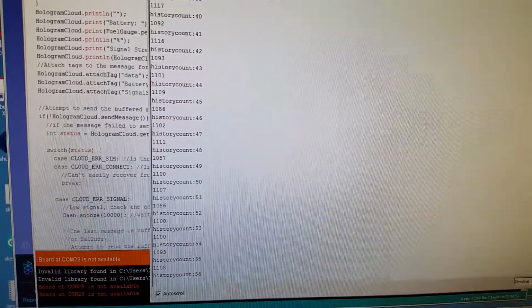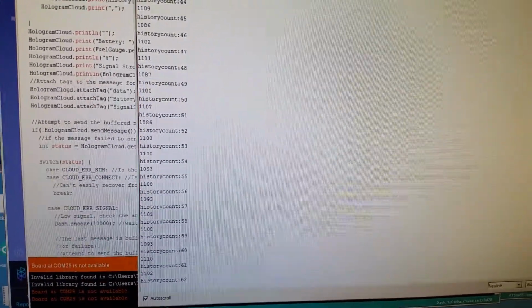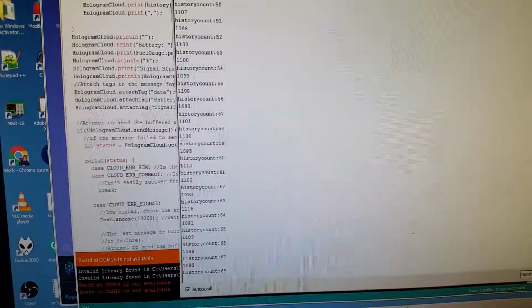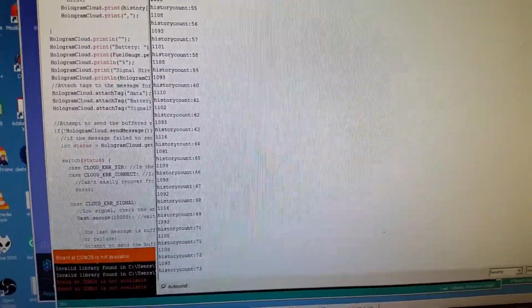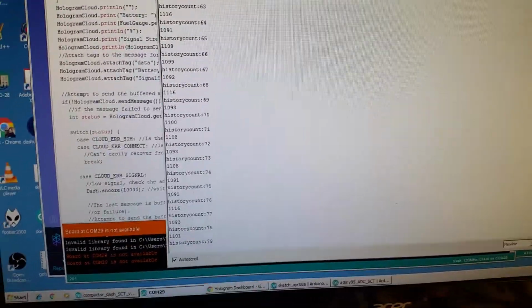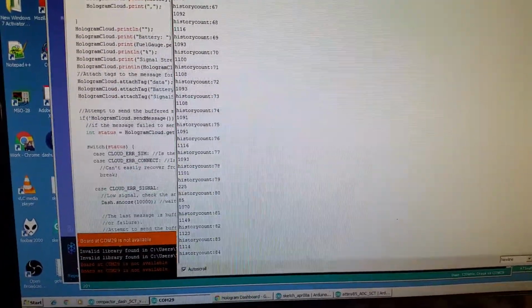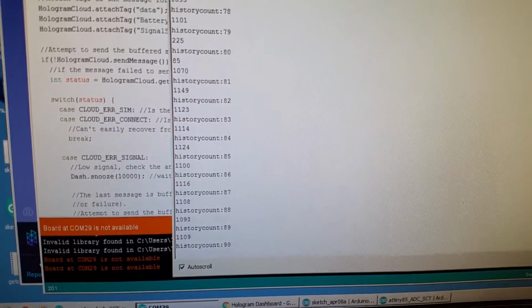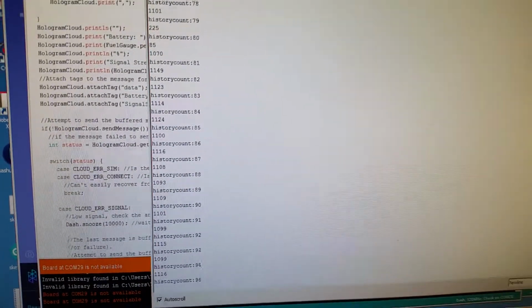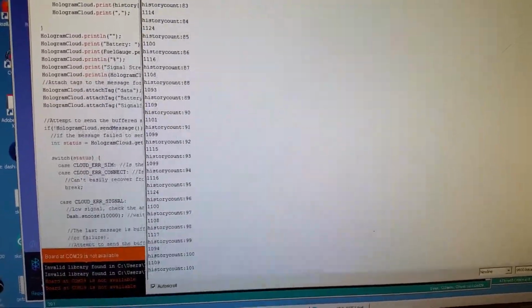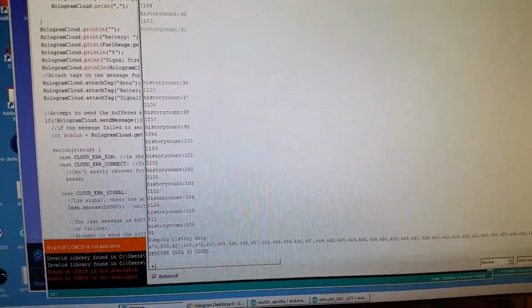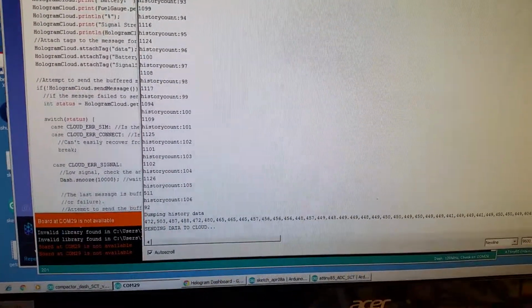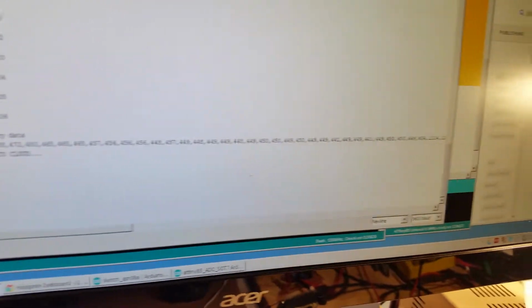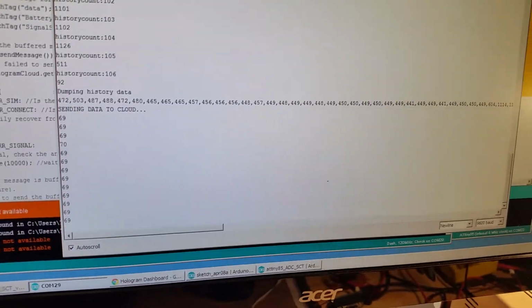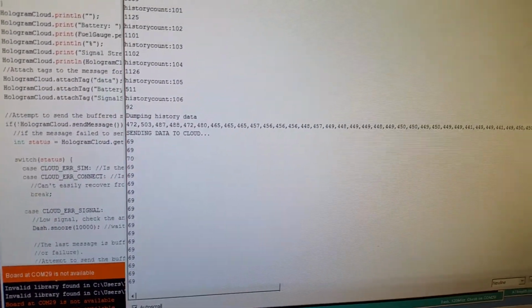Once the history count goes above 20, that will be considered a data point, and that will be sent out. So as long as we have more than 20 history points here, when I turn the power off, and I turn it off for just a second, it'll resume and pick up where it left off and continue recording that as one block of records. But if I turn it off, and it stays off for more than 2 seconds, you can see I get this big long line of all the data points, and then that gets sent out to the cloud. You can see it was sent out to the cloud there.